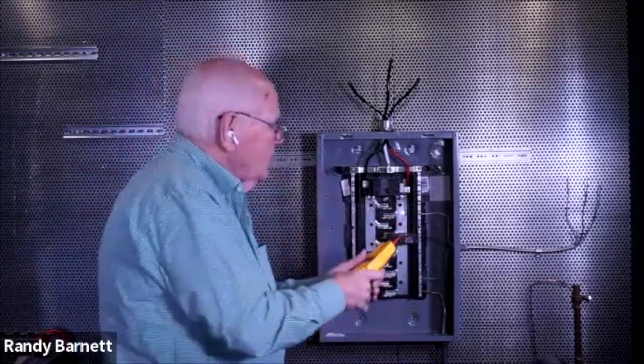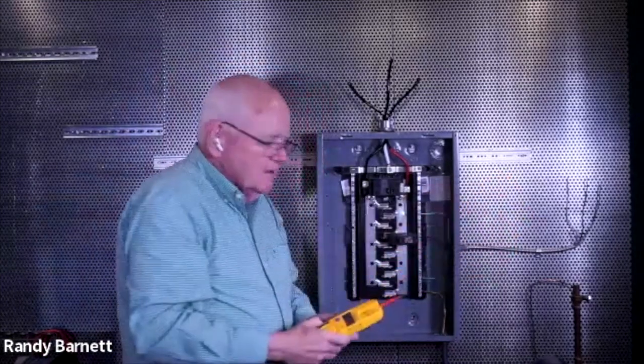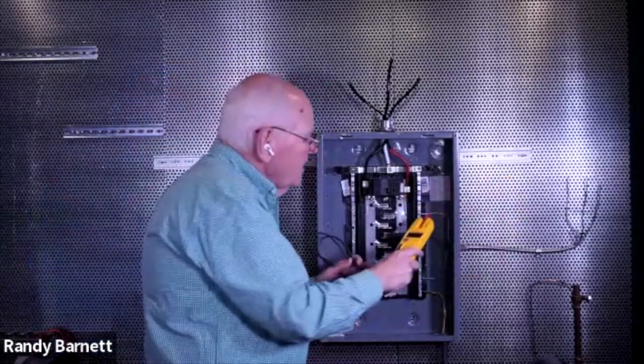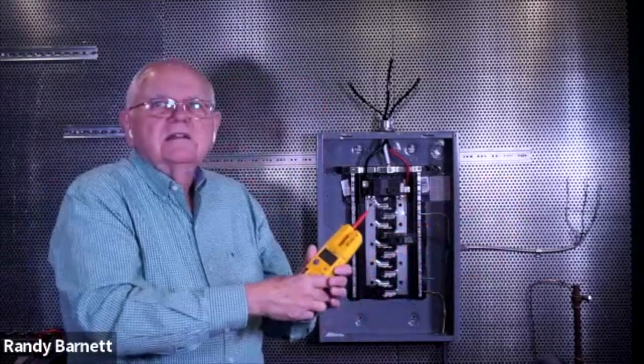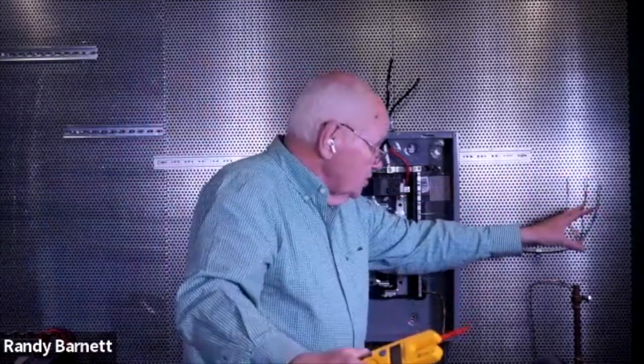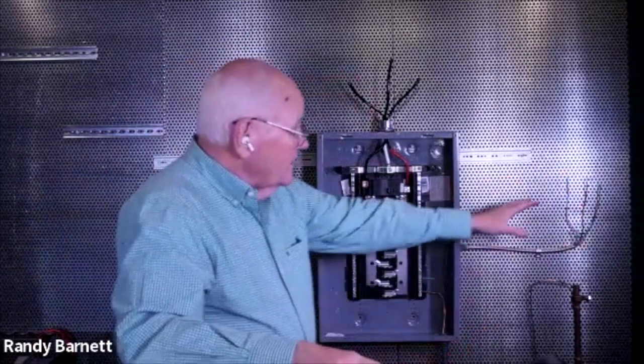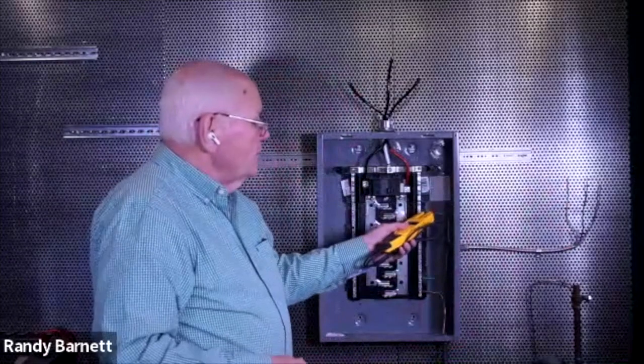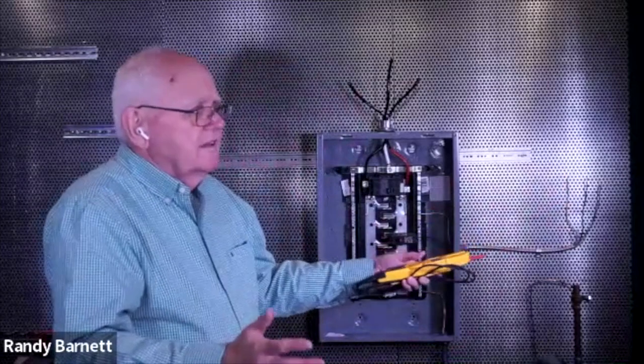That can become an issue down here when I'm on my neutral wire. I'm running out through some MC cable right here going out to my fictitious load over there. But the neutral conductor also has to carry some harmonic currents, which is another whole topic to itself, if I have a lot of digital loads that I'm supplying. And so to carry those neutral currents back, I may have to oversize my neutral conductor in my MC cable, for example. So for instance, I can buy MC cable with the ungrounded conductors 12 AWG and a number 10 neutral wire in that same MC cable.